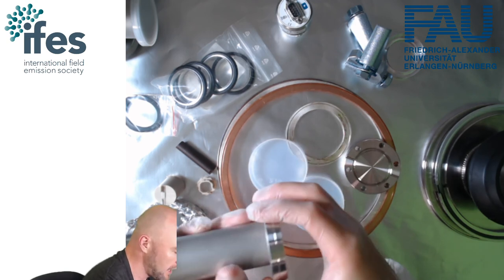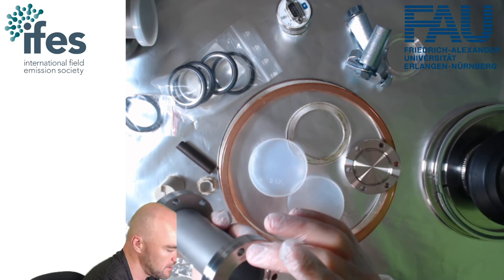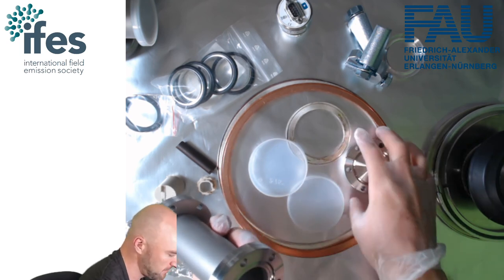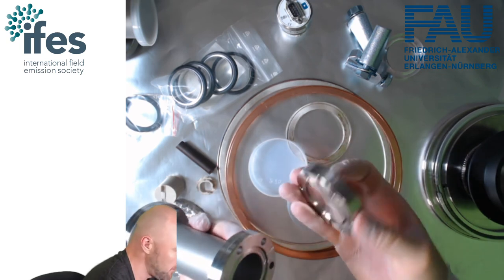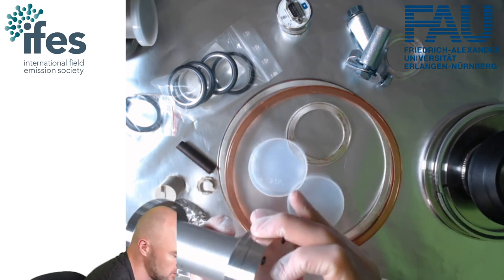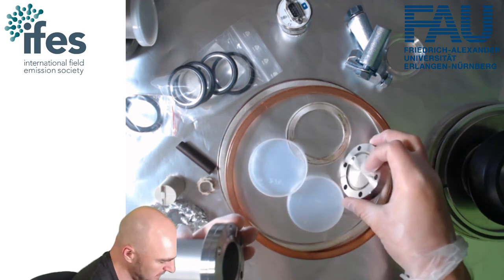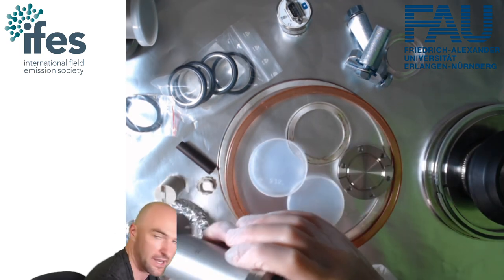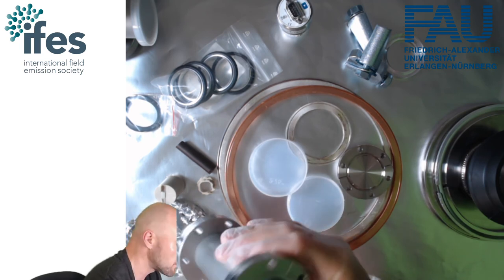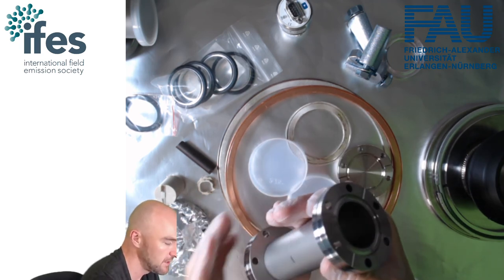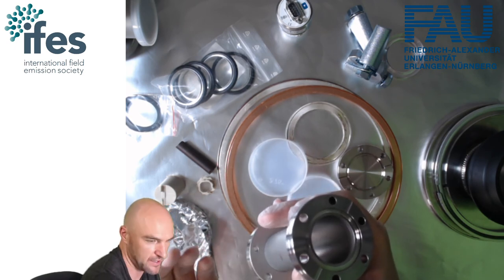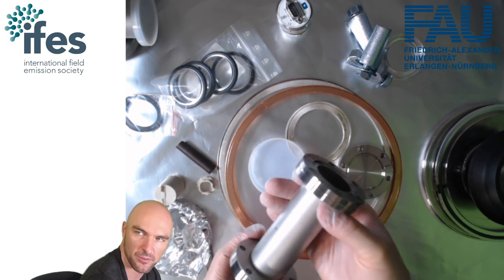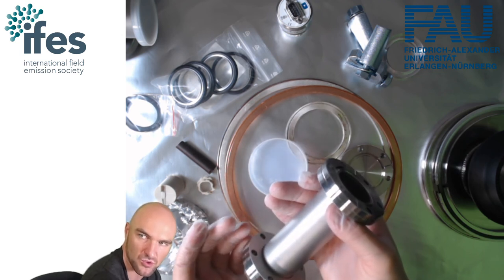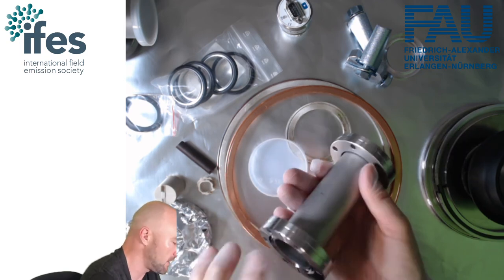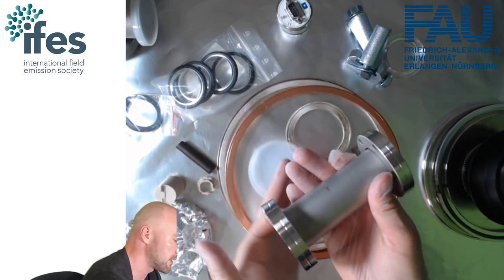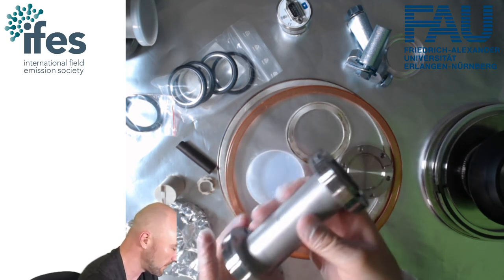The flanges themselves can either have a through hole, or they can be tapped, so they can have a thread in there. If you have a thread, it becomes pretty convenient to put a flange on. You just put the flange on and put the screw in. But the reason why we usually avoid tapped flanges is that if you bake your system to high temperature and one of the screws seizes, you essentially have to throw away your chamber, because you're not going to be able to open the screw and get rid of it. If that happens in a flange like this, then you can just come with a bolt cutter and cut open all the bolts around it.